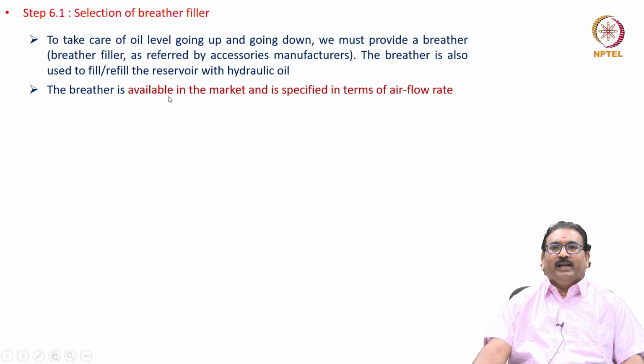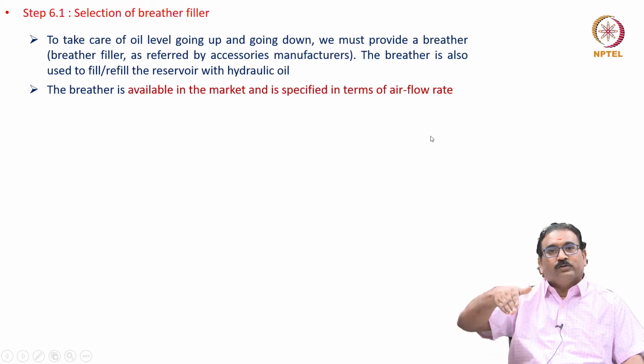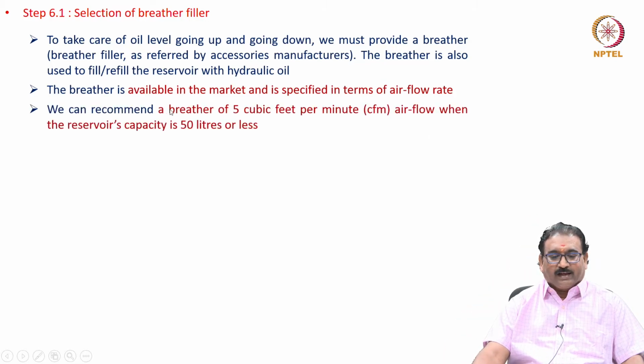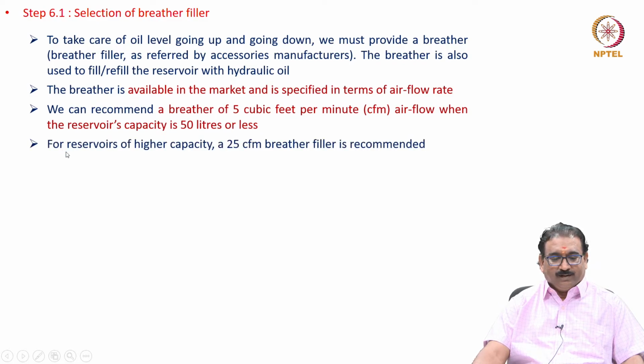The breather is available in the market and is specified in terms of airflow rate passing in and out. We can recommend a breather of 5 cubic feet per minute CFM airflow when the reservoir capacity is 50 liters or less. For reservoirs of higher capacity, a 25 CFM breather filler is recommended.